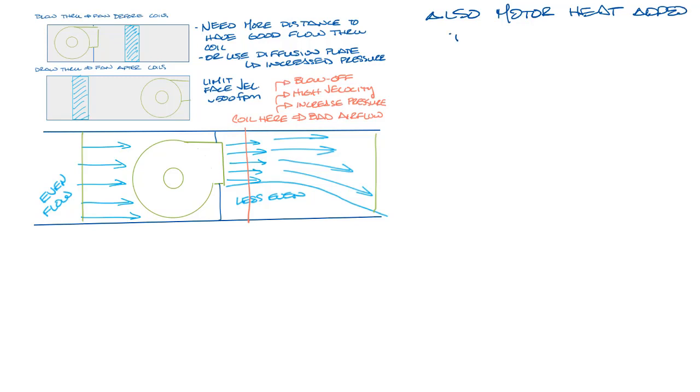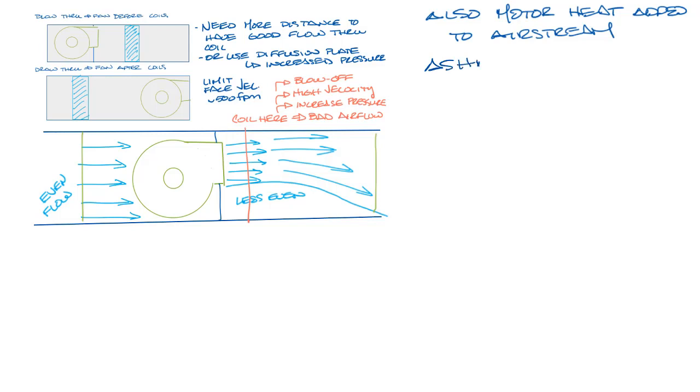In a draw-through arrangement, the heat of the motor will be added to the air stream just as it enters the ductwork. In a blow-through arrangement, the heat of the motor will be added to the mixed air that's coming into the cooling coils. This can add a couple degrees to the air stream. There is an equation in ASHRAE Handbook, HVAC Systems and Equipment, which tells you the temp rise across the fan. It's in chapter 21.7.